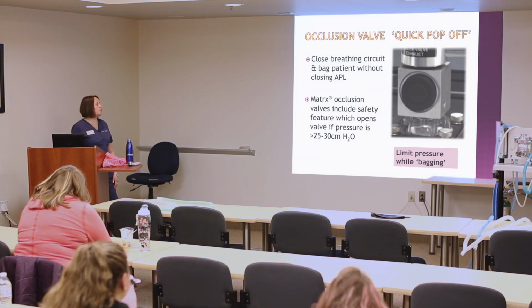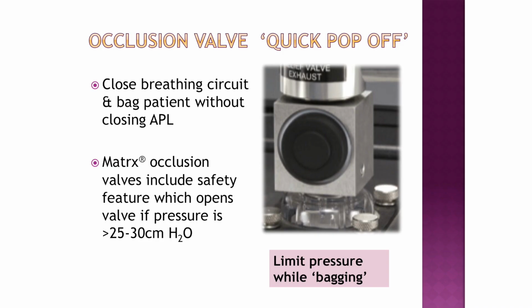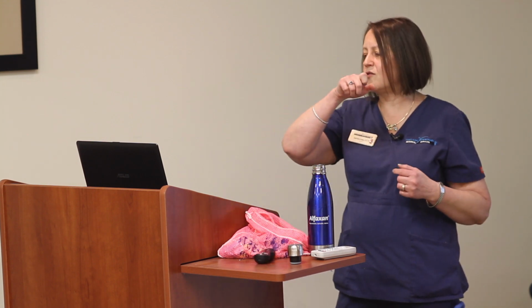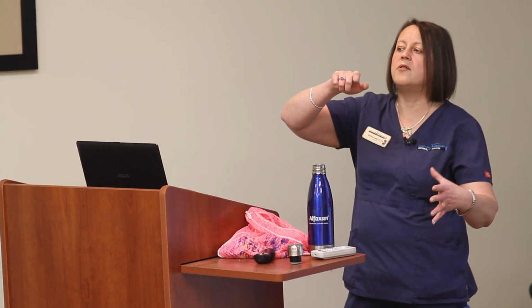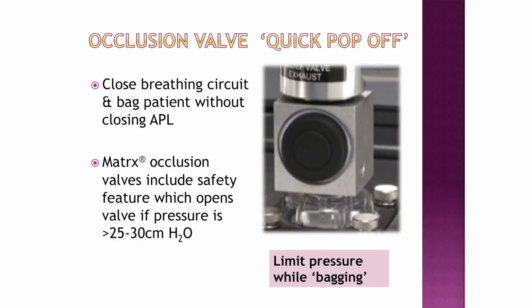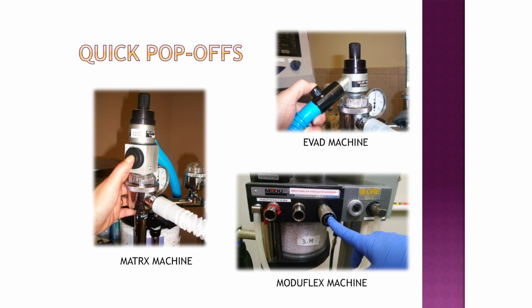Now, I will tell you too that our Matrix machines do have this quick pop-off here, and this one also lets go at 30. So when you're pushing that button down, in a square like a dice, if you try to bag over 30, this particular pop-off will let the breath go, not the quick pop-offs that we use on the other machines. So quick pop-offs, this is the Matrix machine. This one will pop off if you try to squeeze over 30. This one will not. This is what I was talking about. It is possible for you to hold this down and give a breath over.